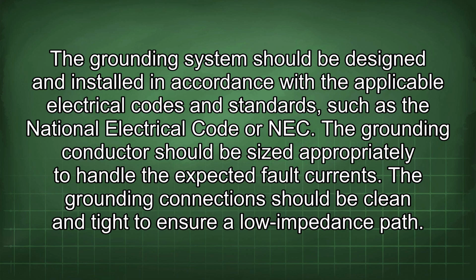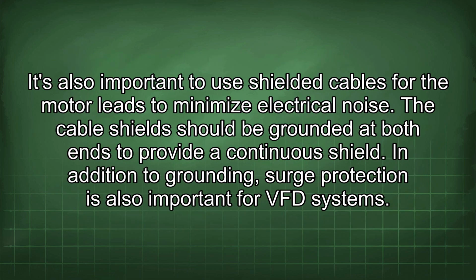The grounding conductor should be sized appropriately to handle the expected fault current. The grounding connection should be clean and tight to ensure a low impedance path. It's also important to use shielded cables for the motor leads to minimize electrical noise. The cable shield should be grounded at both ends to provide a continuous shield.